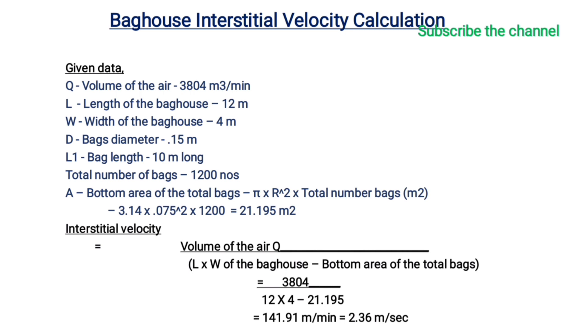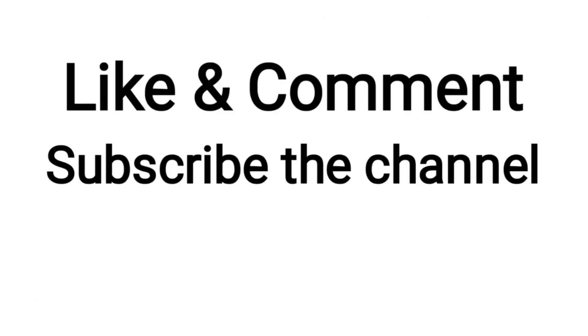Next, based on the above given data, we calculate the interstitial velocity. Interstitial velocity equals the volume of the air divided by the length and width of the bag house minus the bottom area of the total bags. Based on the data and formula, the interstitial velocity is 141.91 meters per minute or 2.36 meters per second. Hope you understand what interstitial velocity is and how to calculate it. Thanks for watching — subscribe to the channel for more videos.